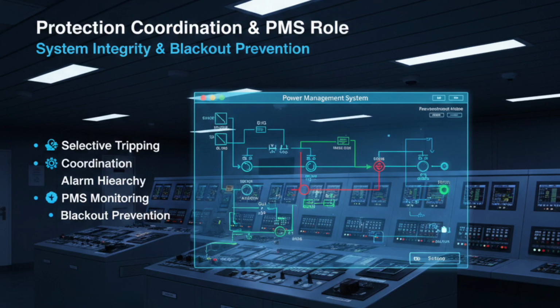Protection coordination or PMS role. Protection coordination ensures only the faulty generator trips, not the entire system. Selective tripping prevents blackout. The power management system monitors alarms, logs data, and automatically starts standby generators if needed. PMS also ensures alarm hierarchy. Minor fault gives warning, major fault triggers trip. Proper coordination ensures safe and uninterrupted marine operations.